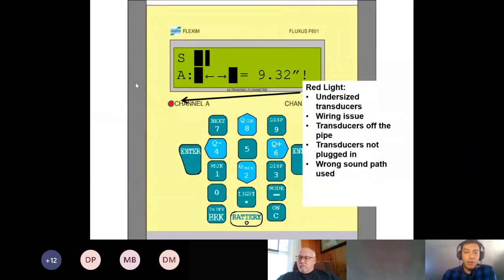If you have a red light, that's a different story. This could also be undersized transducers. They're just getting no communication between each other. It could be a wiring issue. So maybe check your terminals, check your J-boxes if it's a dedicated meter. That's not too relevant for the portable meter. Again, make sure they're plugged in.